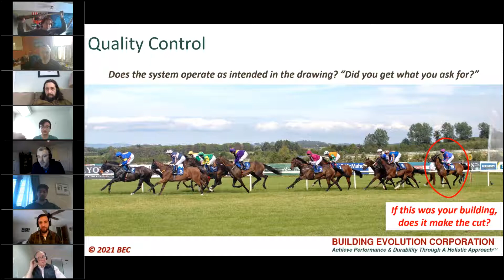Here's an example. We were brought into a project where they asked us to come in and commission a building after it was built and being operated, and for some reason the electrical bills were substantial. All electric building, heat pumps to each unit, ERV - so it sounds good, but that ERV has got an electric resistance for heating the air. The set point they have it at means that ERV is now heating the space in the building, and because it's overheating the halls, those heat pumps are actually not working, or sometimes going into cooling. So the building's being heated by electric resistance and a whole lot of electricity.